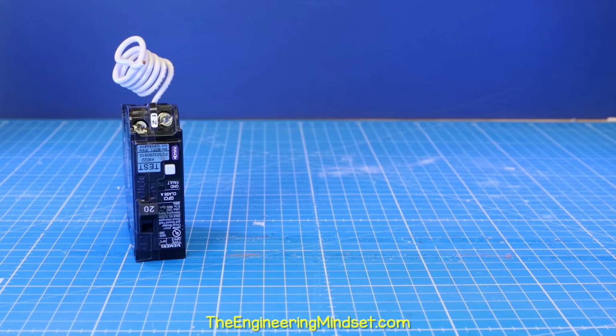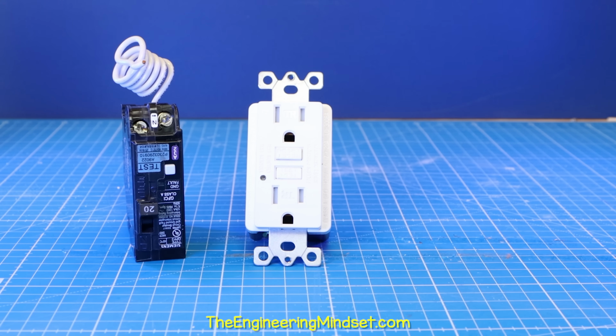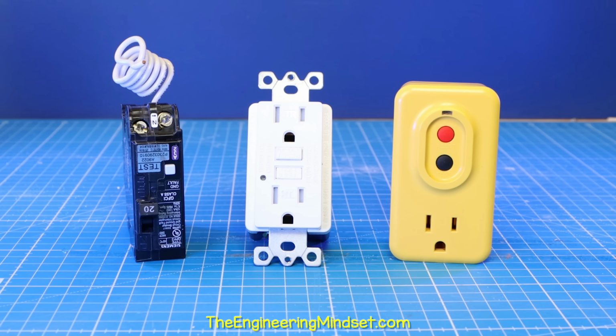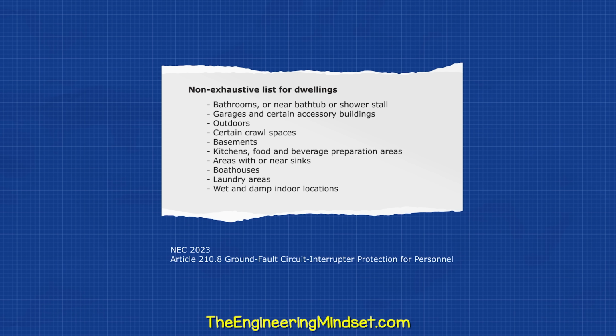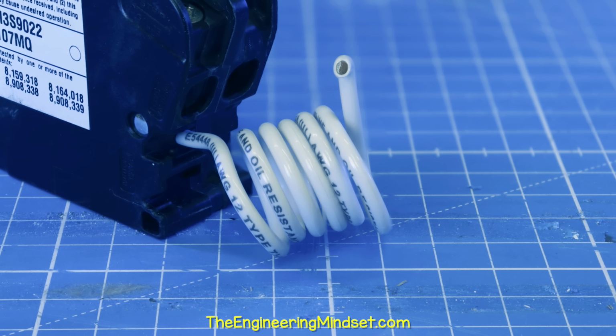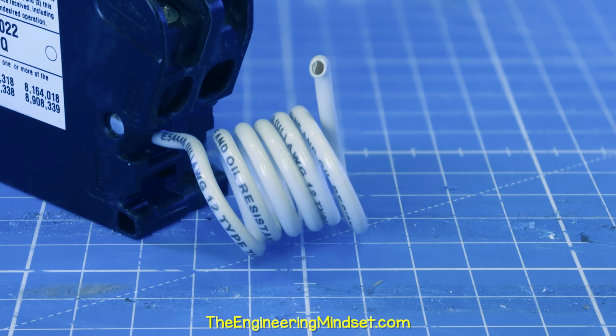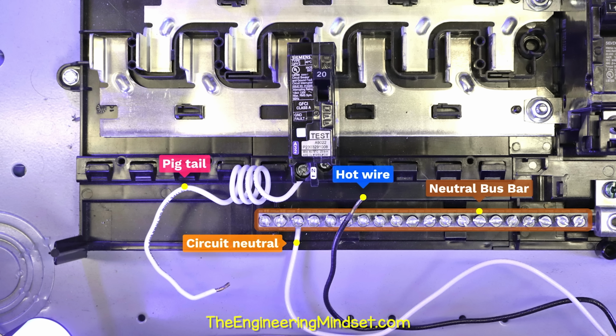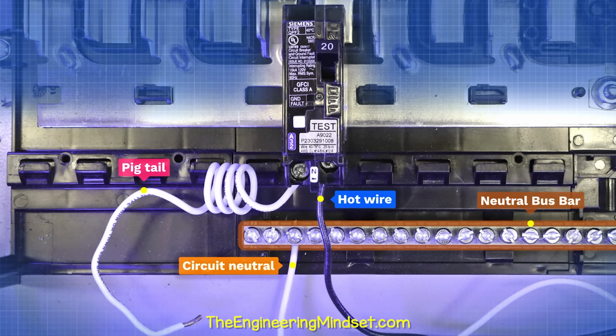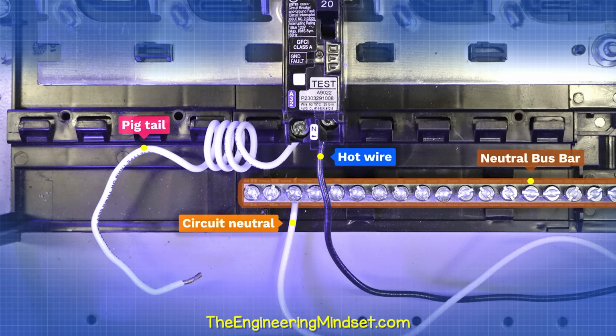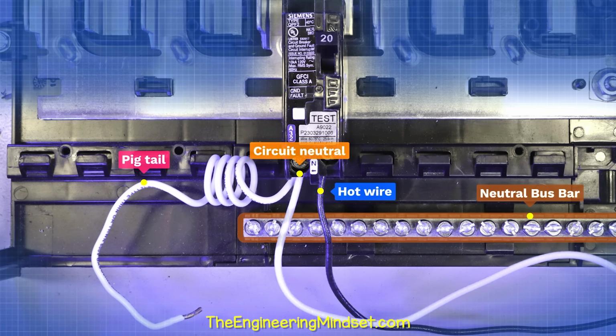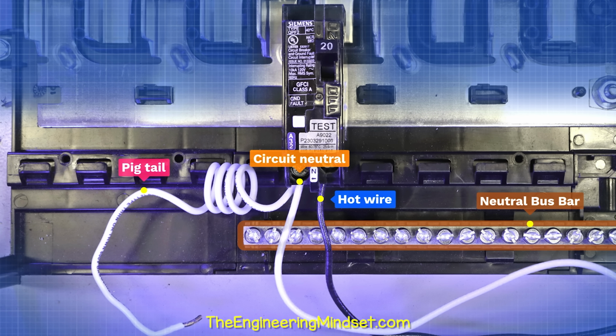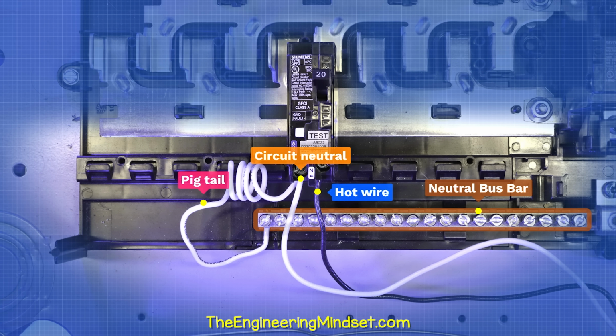However, we can use GFCI breakers, outlets, and plug-in devices which will prevent most of these faults. GFCI protection is now required in most parts of the home by the NEC. The GFCI breaker has this coiled neutral wire built in. This breaker fits into the panel as normal, but the circuit neutral will now connect into the neutral terminal on the breaker, and the pigtail will then connect into the neutral bus bar.